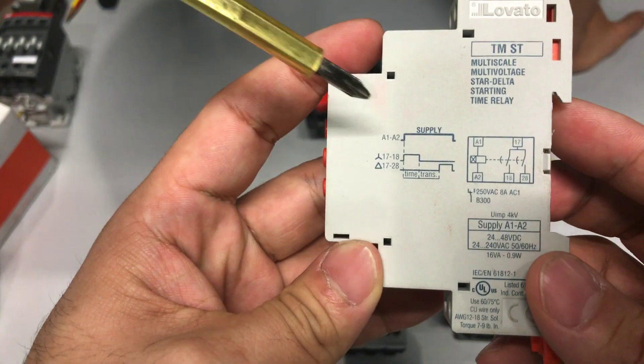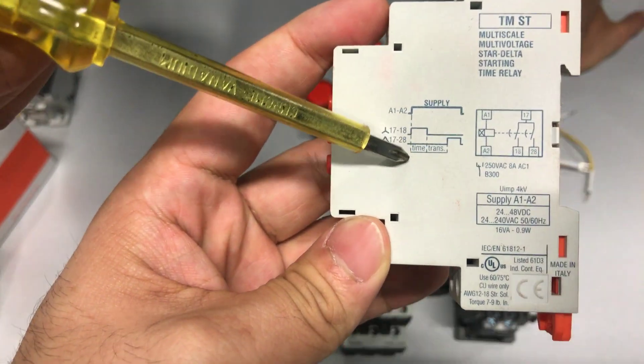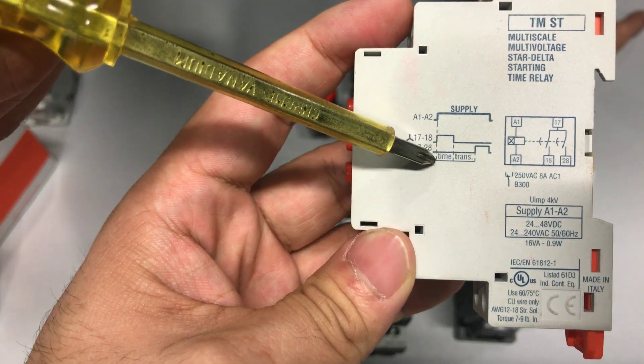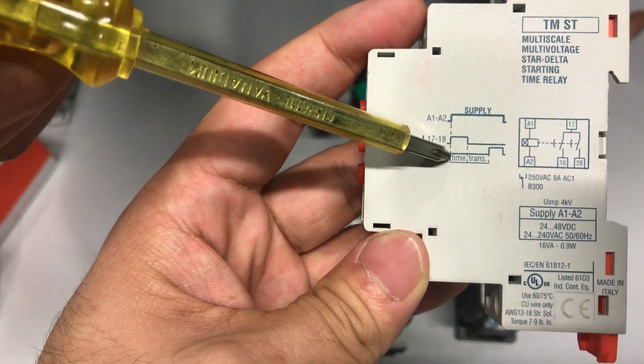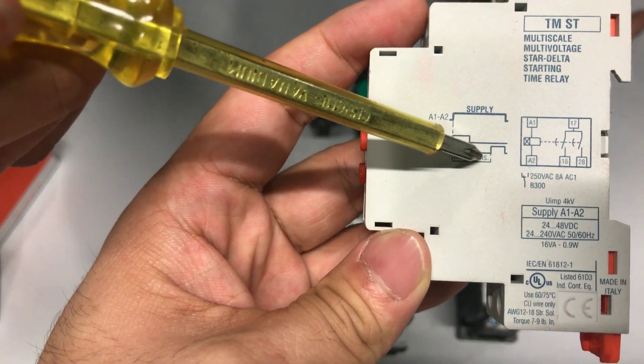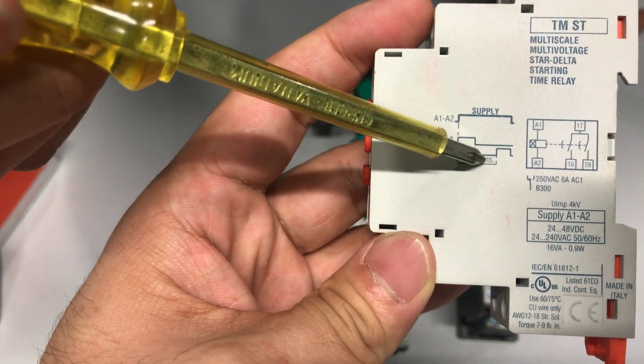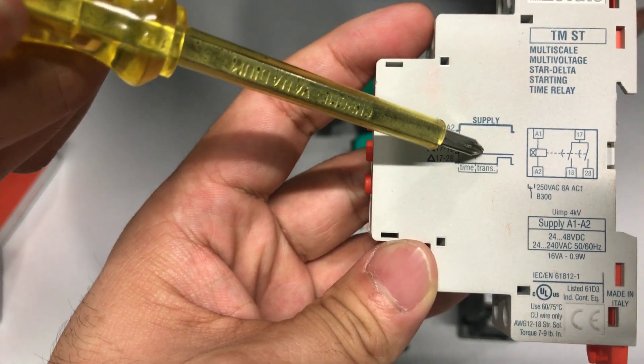So the star time period can be set by the first and the second dial, and the first one acting as the multiplier. Then you set the transition delay with the third dial. The maximum transition time you can set for this timer is 300 milliseconds.